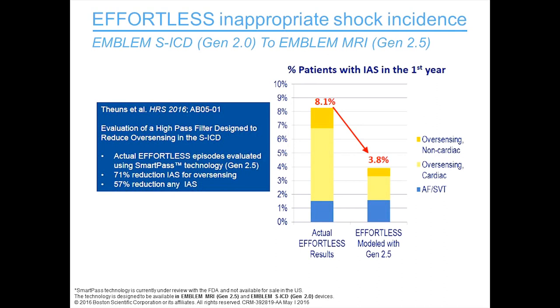So inappropriate shocks in the first year, what we've learned from the Effortless Registry, that was about 8% of patients. Based on those rhythms and the improved discriminators of model 2.5 of the device, we expect that rate to drop to 3.8%, truly comparable to that of transvenous systems. So the problem of inappropriate shocks will be neutral compared to transvenous systems when we move into Gen 2.5. We're getting better, and the device is climbing the learning curve quickly with programming sophistication.